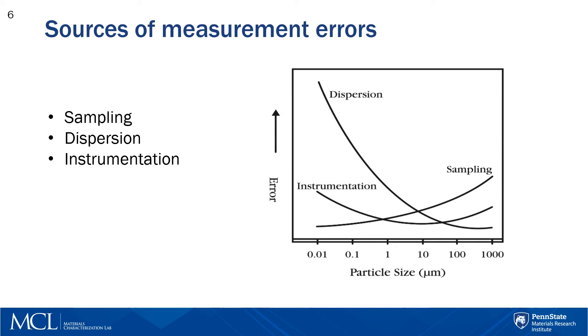Other things to consider when doing laser diffraction are sampling and sample dispersion. There are three main sources of error: sampling, dispersion, and instrumentation. As you can see from this plot, proper dispersion is very important in the smaller size range, while if you have larger particles or a very wide particle size range, then sampling becomes progressively more important.